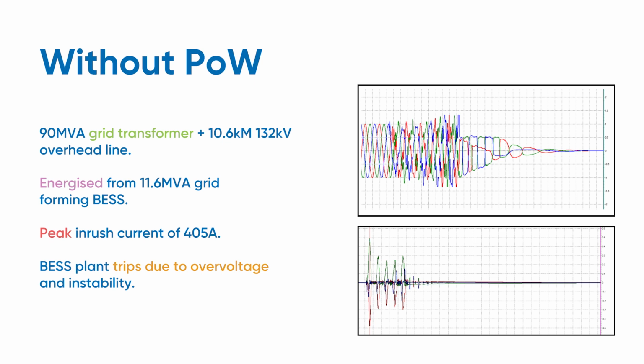You see the voltage go very unstable, and the BESS plant effectively tripped to protect the battery energy storage inverters because of the grid instability. So obviously that's not ideal. We've got this big blackout. We need to get critical power back on to hospitals, to businesses, to homes. We tried to do it, and it all kind of de-energizes again. So we need to have a solution in place that's reliable.